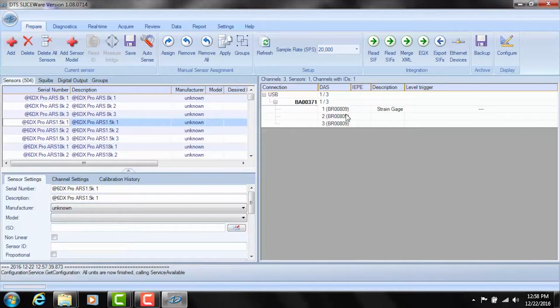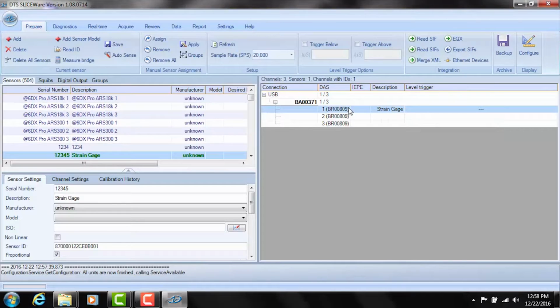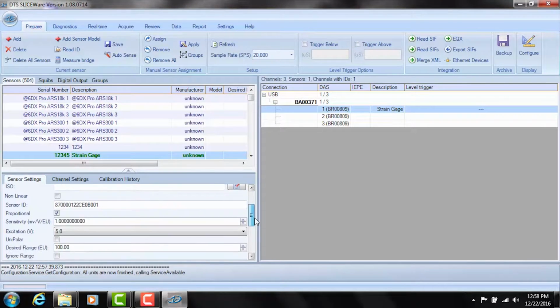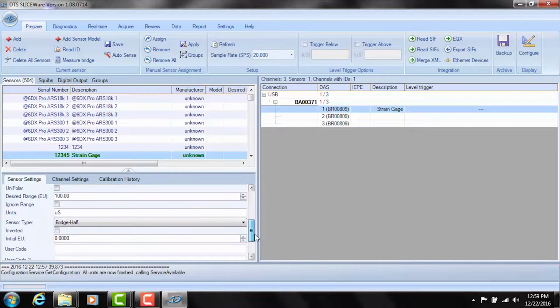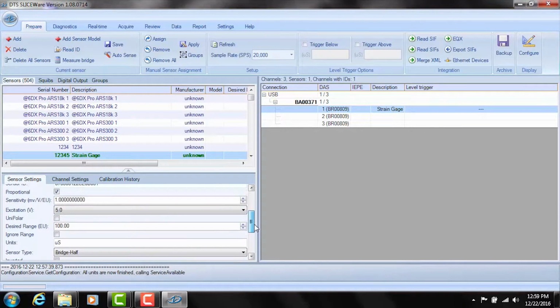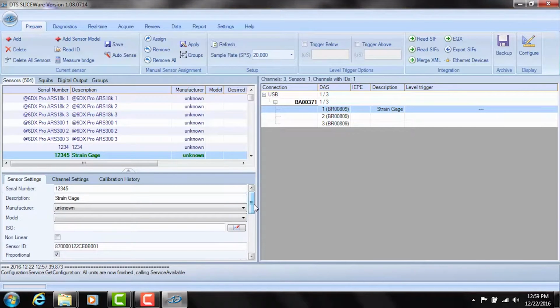I'm going to go back over to the right side of the screen and click on channel 1 on the bridge and click on the strain gauge. Here again, if you go to the left side, you'll see we've got specific information about that strain gauge, including things like serial number, the type of sensor it is, sensitivity, excitation voltage, and so on. Okay, so we have our sensor recognized, and we're ready to go.